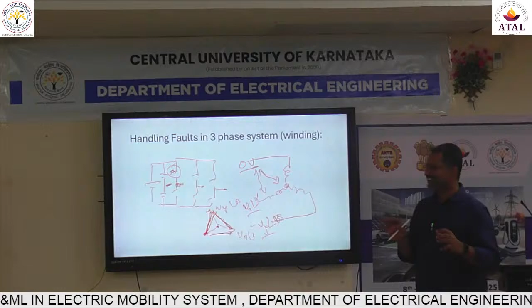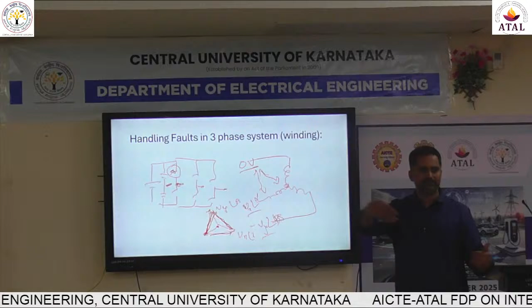So what you have to look at is, when I'm trying to tap here, what is the requirement of the capacitor? Typically these capacitors were designed to take only ripple currents in any system. But when you connect a phase there, you are going to draw the phase current from the capacitors. This is a very serious problem in single phase also, where 2 times the fundamental frequency capacitors will be carrying current, causing balancing problems and all of those issues.